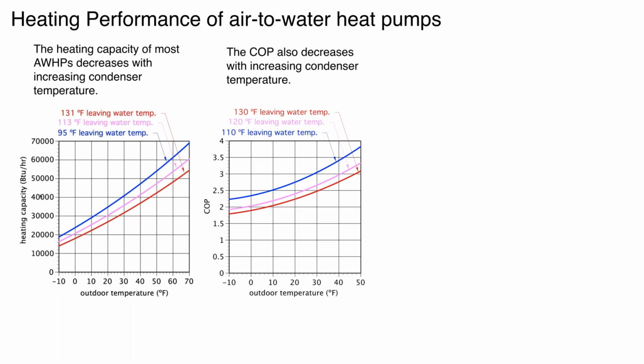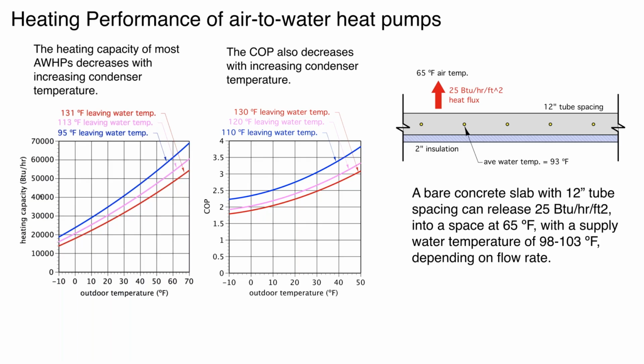So a bare concrete slab sets the stage for relatively low water temperatures. Just to give you a feel, I worked out one scenario here. Say we have a 6-inch slab, 12-inch tube spacing, and we're trying to get 25 BTUs per hour per square foot off the top of that slab, going into a space at 65 degrees. I picked 65 because in many of these commercial fabrication buildings and garages, people are working at a higher activity level. Typically, they don't want the temperature to be 68 or 70 degrees. They consider that too warm. Highway garages, we've seen them run anywhere from maybe 55 to 65 degrees because the people have more clothing on, or, as I say, they're working at a higher activity level.